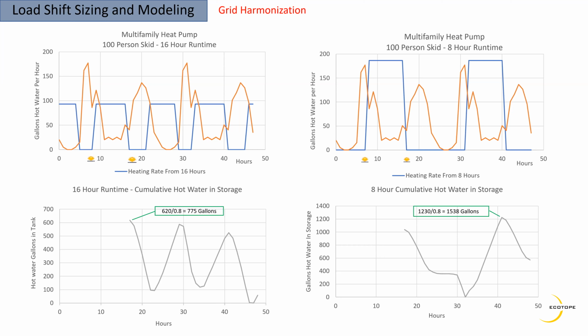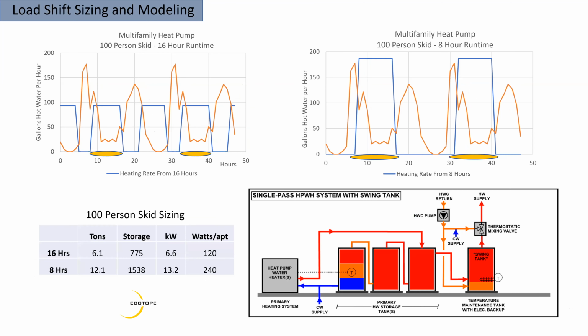So runtime is a really critical piece of how you size these systems, and that will be integral to the sizing tool. Just to show an example of the two: down on the right is a typical load-shiftable thermal battery. This feeds the swing tank. We've seen these kinds of schematics before, or if you haven't, that's sort of what the system would look like. And the table on the left shows the impact of the two different sizings.